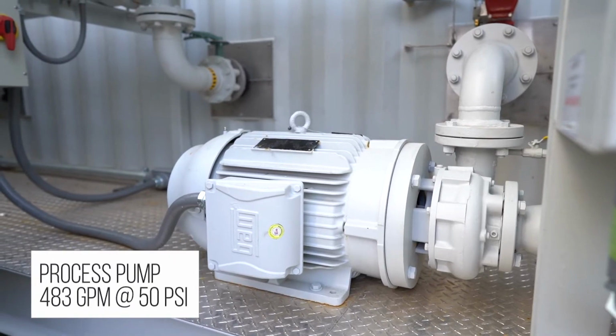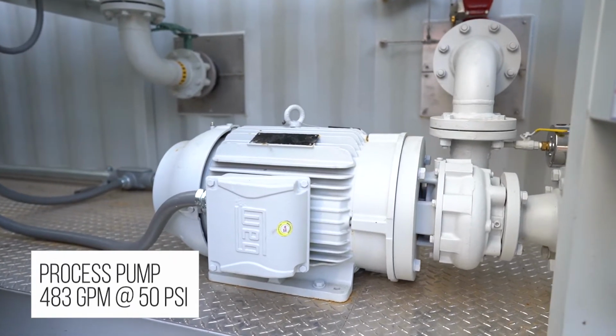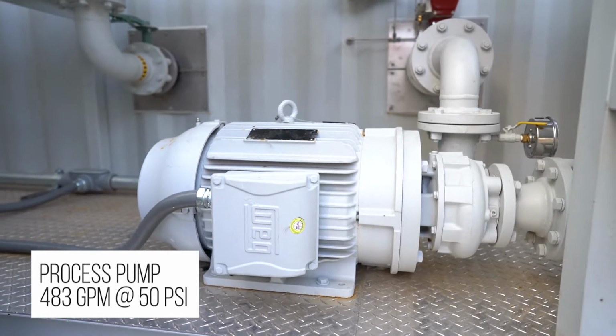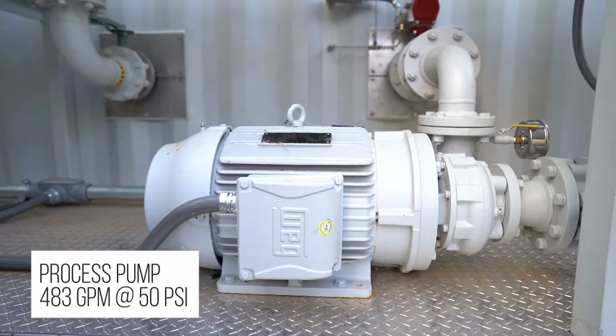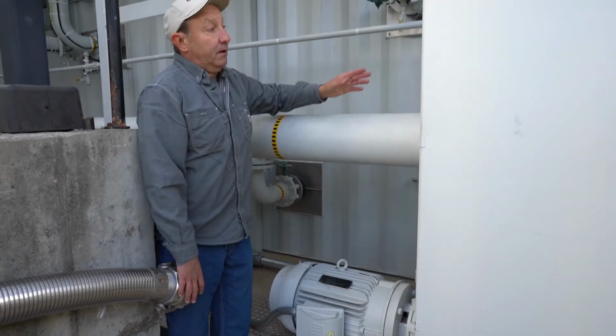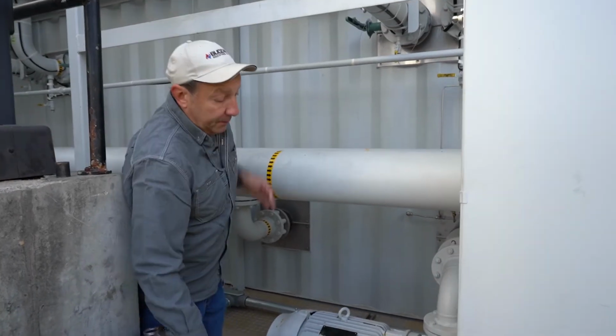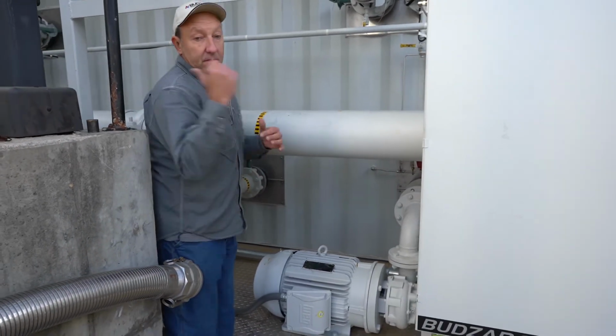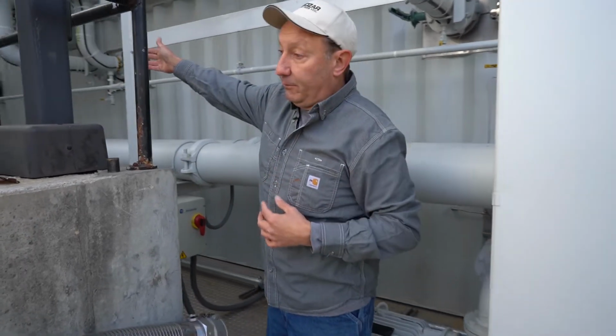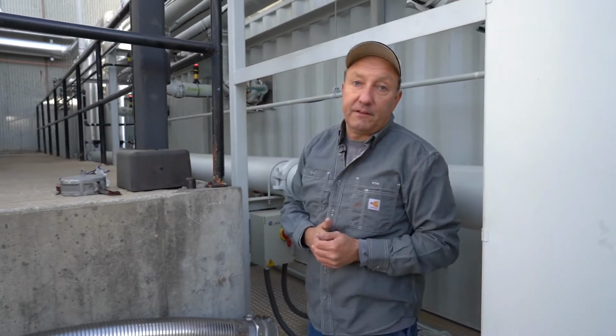Each process pump, glycol pump, is designed for 483 gallons per minute at 50 PSI. Each pump supports the independent circuit. For example, this is chiller pump 1, chiller pump 2, chiller pump 3 down at the end. Each one is designed equally for the same flow rate and pressure.